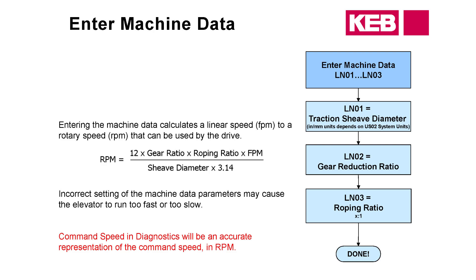Check to make sure you're going the correct speed. Run the car on inspection and look at the command speed, then look at the motor speed — the feedback coming back from the encoder — and make sure those two are close. If they're off by a factor, you may have to adjust your sheave diameter or gear reduction ratio.